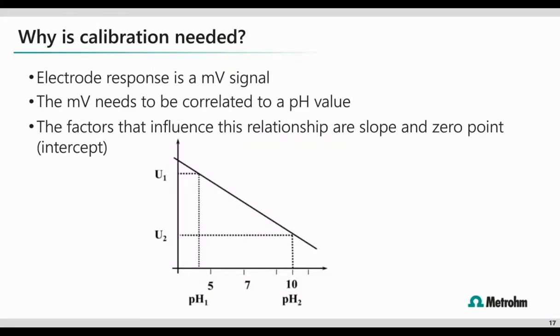Next up, let's talk a little bit about calibration and why it's needed. Think of this simple image on your screen now as a 2-point calibration. We have 2 buffers, which give 2 potentials, that's your U1 and U2, at 2 pH values, pH1 and pH2. Going back to the beginning, the potential of a measuring electrode can always only be given relative to that of the reference electrode. So in order to compare the systems, we need to use the electrode 0 point, something that we define as 0 millivolts for pH 7. And we also use the electrode slope, which is given to us through the Nernst equation, and that is theoretically defined as 59 millivolts per 1 pH unit.